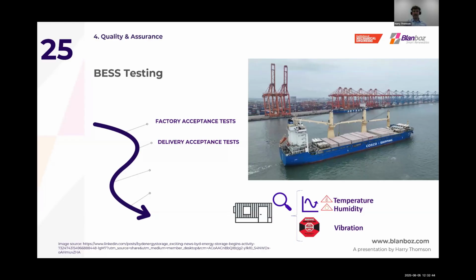Next, we have the delivery acceptance tests. Depending on the Incoterms, which I'll come on to later, these are a test to check that transportation did not cause further defects or any issues. We like to push in contracts for environmental monitoring, because lithium ion is particularly sensitive to extreme vibration as well as temperature and humidity extremes. Once it gets to site, you can check if limits have been breached, and in these cases, you can flag containers that may have performance issues down the line, or in extreme cases, it can lead to replacement or rejection of equipment.